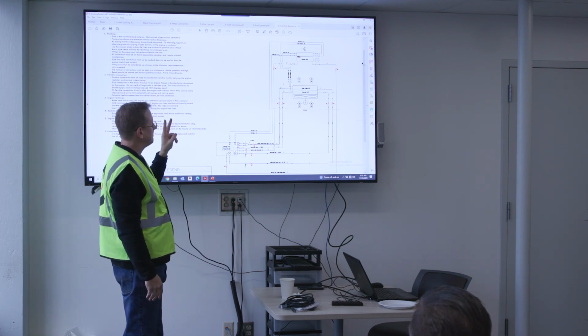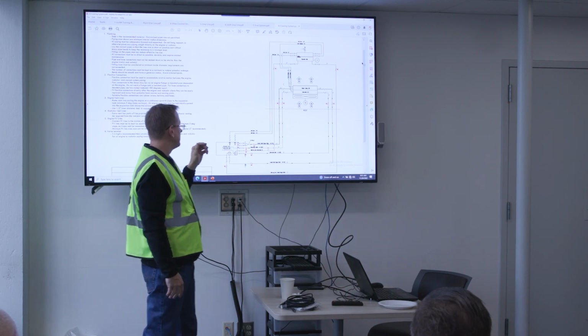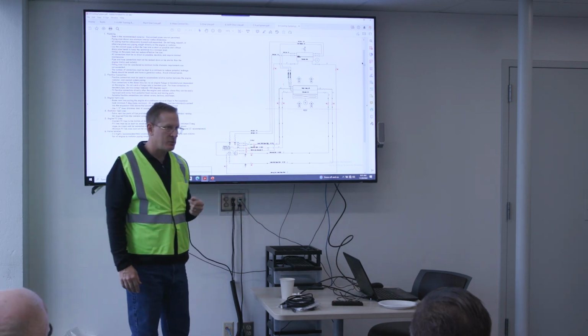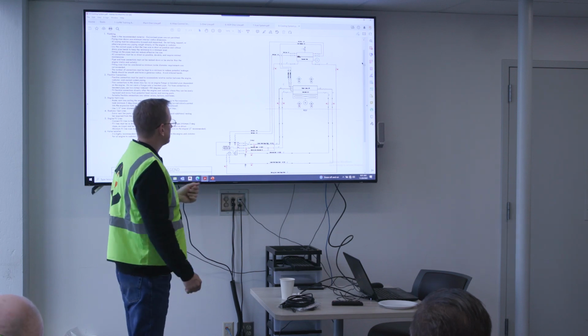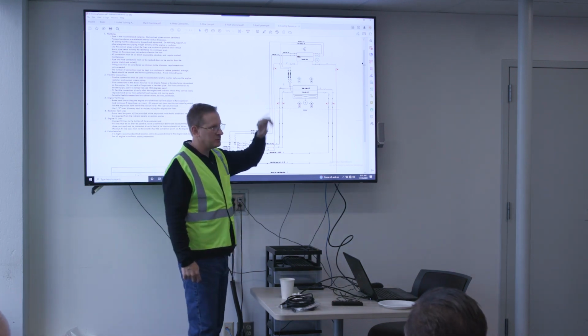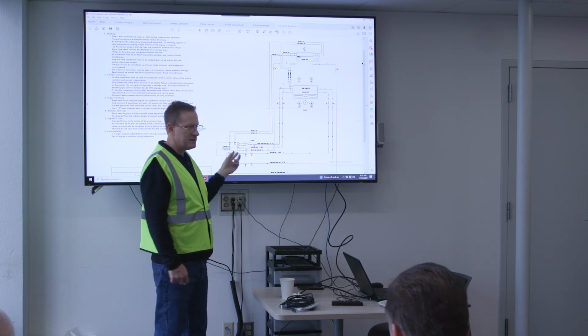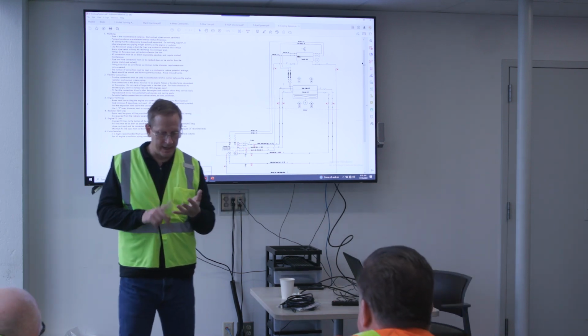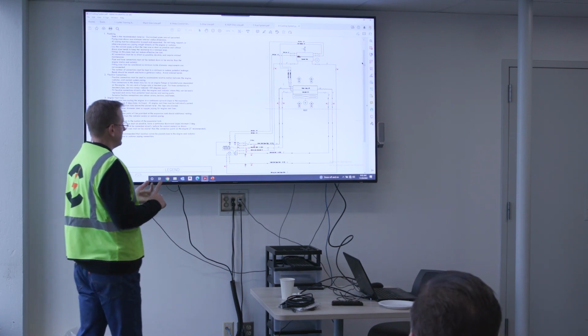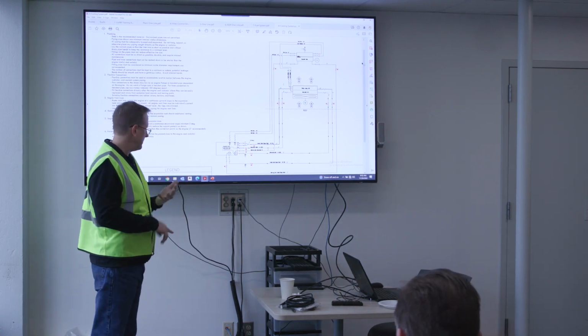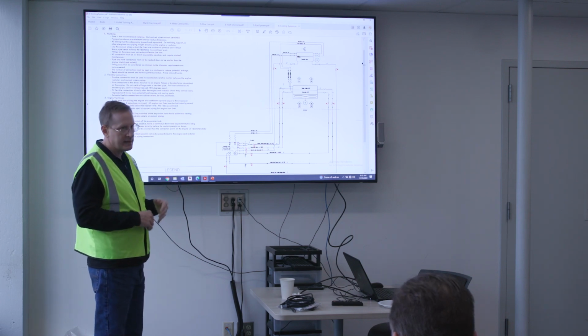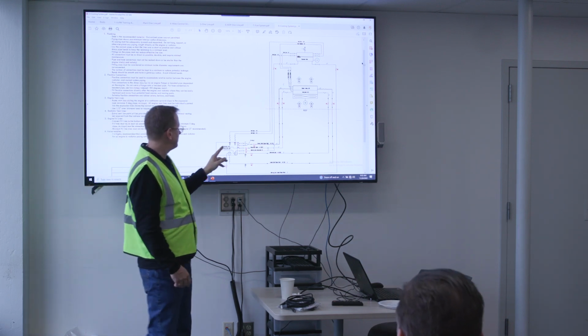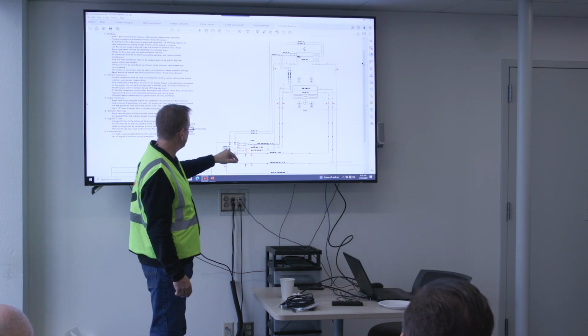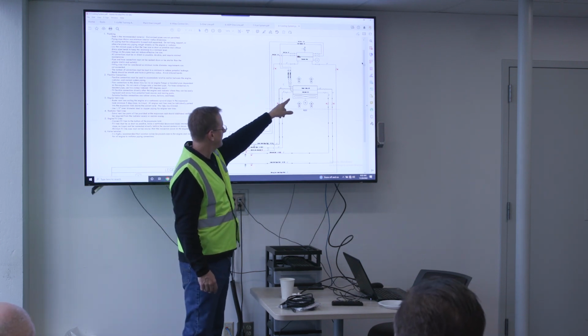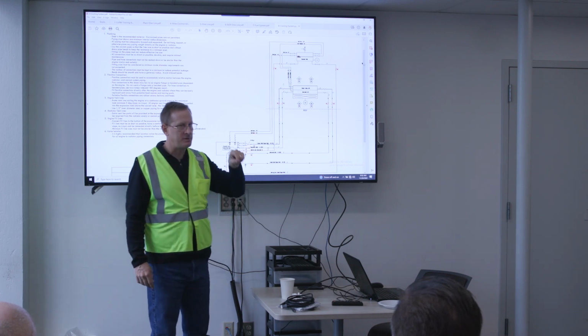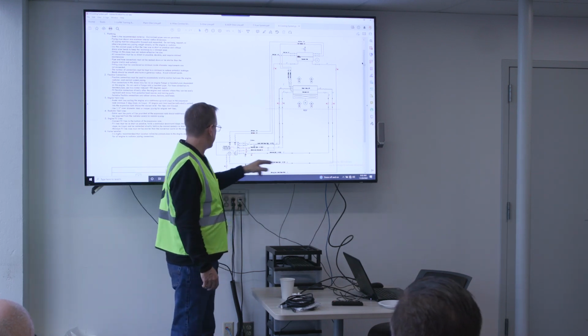So there's 2 sets of piping that you'll see from the engine that will extend all the way to the roof, to the radiators. The radiator itself is a dual core radiator, because the engine is a dual circuit engine. There's a high temp circuit and a low temp circuit. Sometimes the high temp is called jacket water, and the low temp is called the intercooler circuit or AC circuit. But you'll have 2 sets of pipes, supply and return, coming from the engine, going to the radiator, either the high temp or low temp core, and then coming back into the engine.